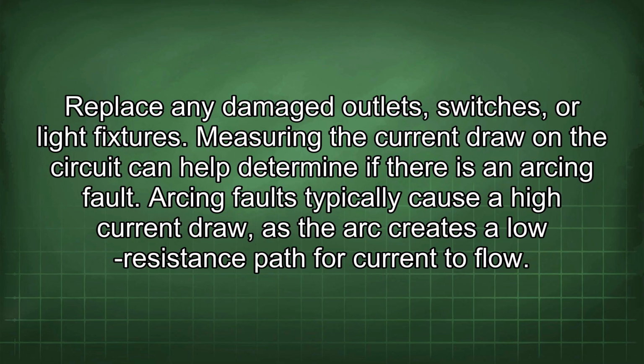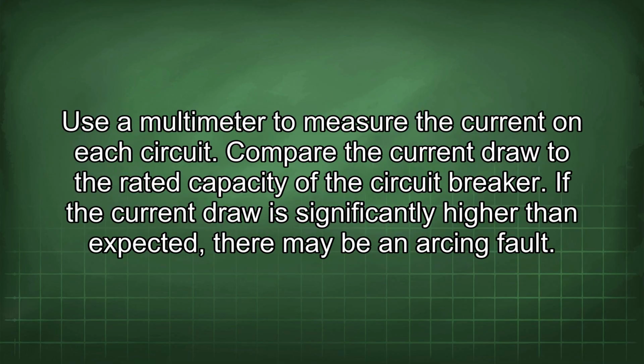Measuring the current draw on the circuit can help determine if there is an arcing fault. Arcing faults typically cause a high current draw, as the arc creates a low resistance path for current to flow. Use a multimeter to measure the current on each circuit. Compare the current draw to the rated capacity of the circuit breaker. If the current draw is significantly higher than expected, there may be an arcing fault.